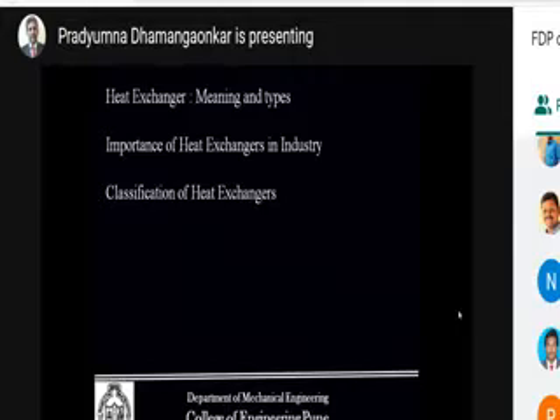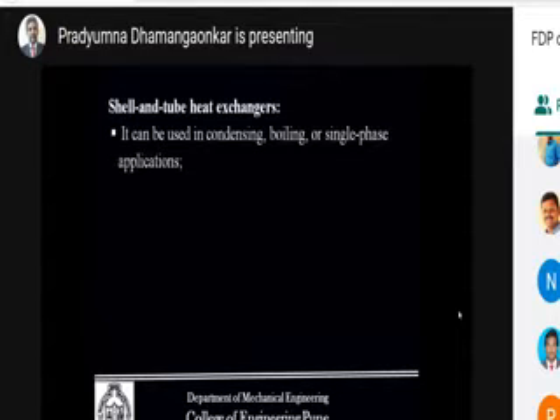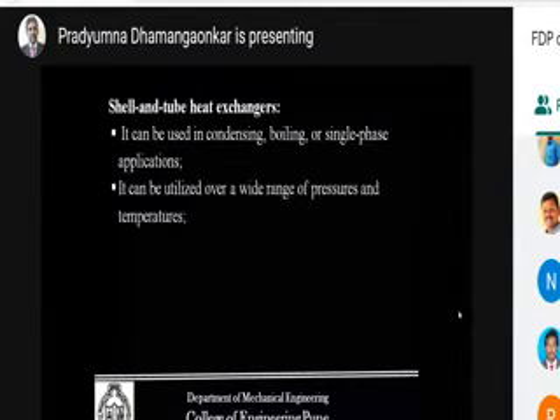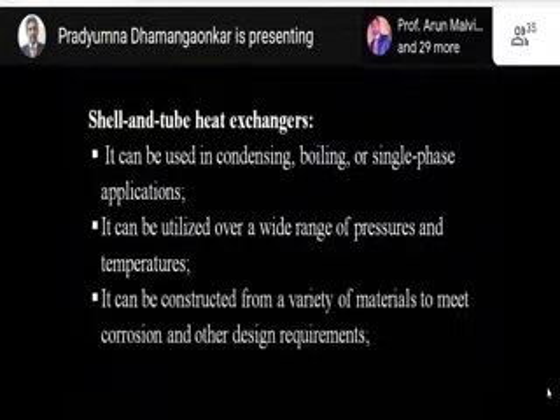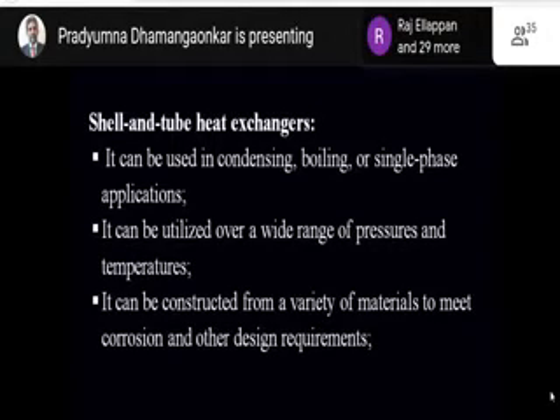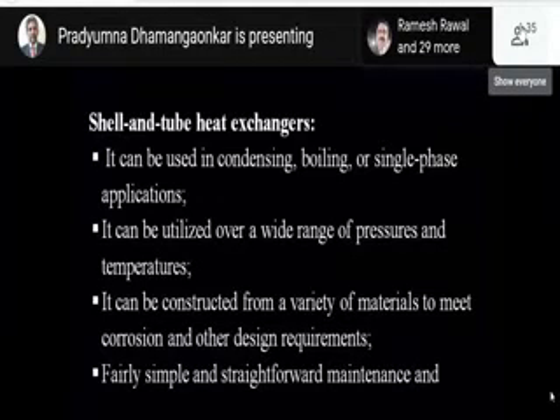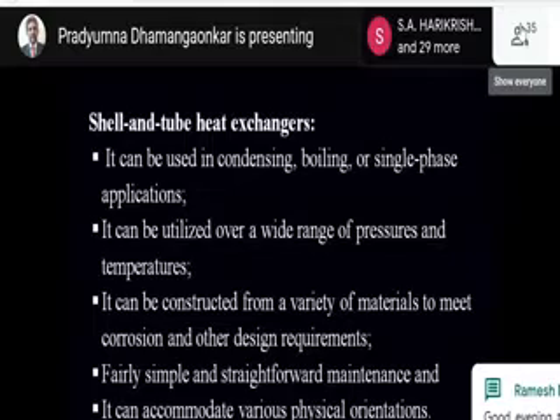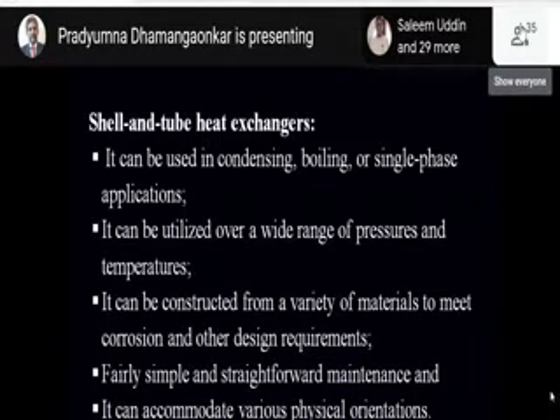But it is said that the shell and tube type heat exchanger is the versatile heat exchanger. It is used in most of the different applications, starting from simple domestic use to huge industrial use. And hence, I will first take into account the shell and tube type heat exchangers. The advantage is that it can be used in condensing, boiling, or even single phase and two phase applications. It can be utilized over a wide range of pressure and temperature. It can be constructed from a variety of materials to meet corrosion and other design requirements. It is simple and straightforward for maintenance as compared to other heat exchangers. It can accommodate various physical orientations, horizontal, vertical, even series, parallel, whatever you want, that can be very well coped with by the shell and tube type heat exchangers.